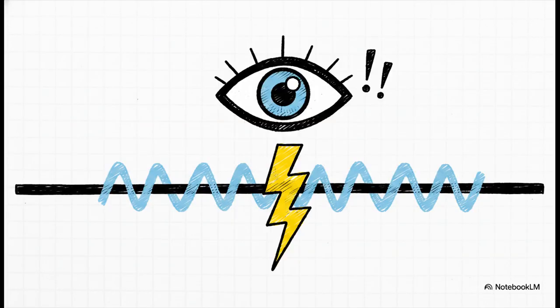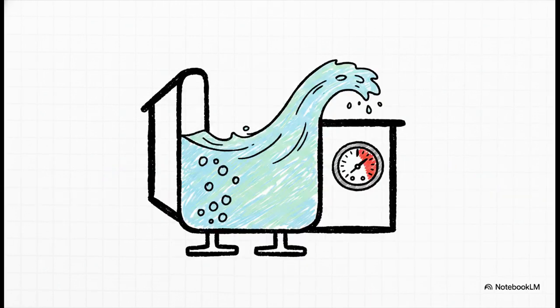The first layer of that shield is electrical protection. Pretty straightforward, right? These are the sentinels that are watching the flow of electricity itself. They're constantly looking for any telltale signs of trouble, like a dangerous spike or a massive surge in the current. Now, the second layer is mechanical protection, and this is where things get really cool. These devices aren't looking at the electricity, they're looking for the physical symptoms of a problem inside the transformer, things like a sudden buildup of gas pressure or a violent rush of oil inside the tank.